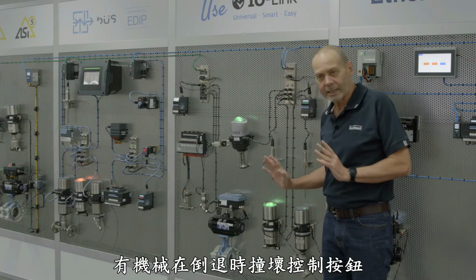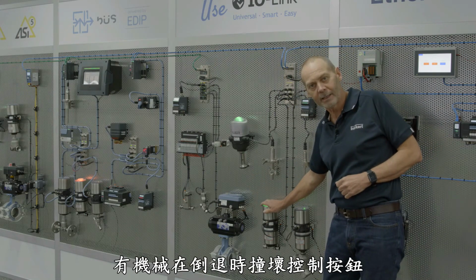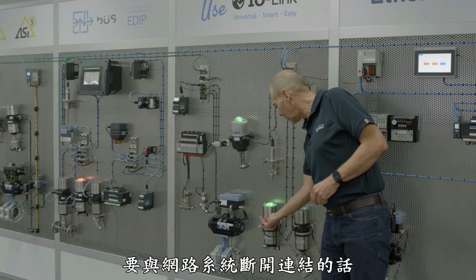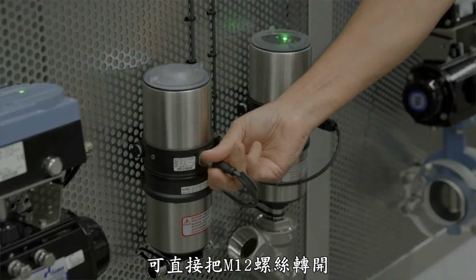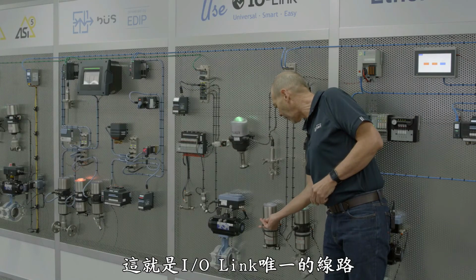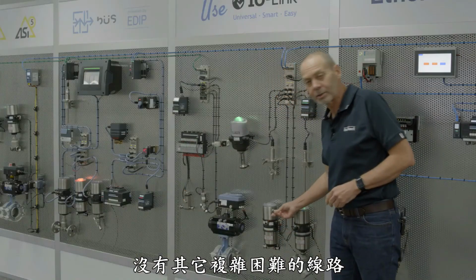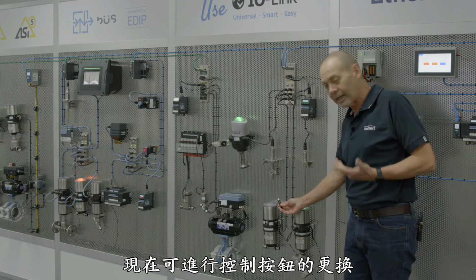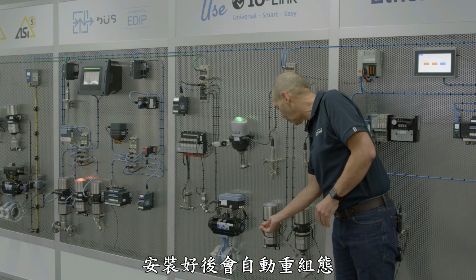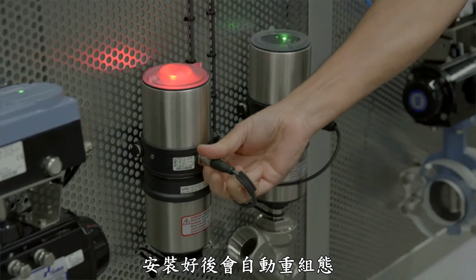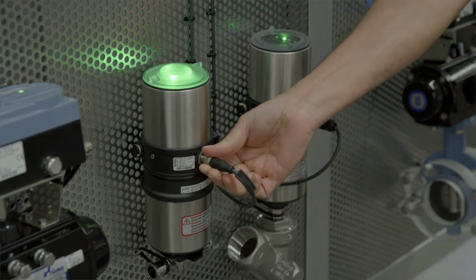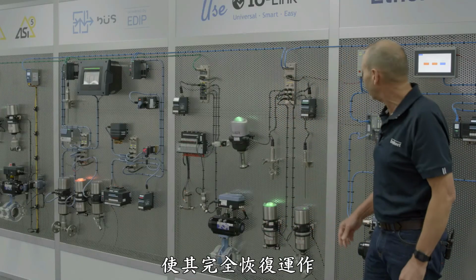So in other words, let's just say a forklift backs into this head and smashes it. So you disconnect the network with a simple M12, which is the entire wiring in IOLink. There is no cables to connect, etc. So that's now, we replace that head, and when we put a new one in, it will automatically reconfigure and make itself fully operational again.